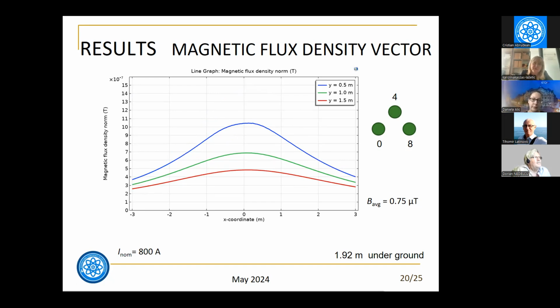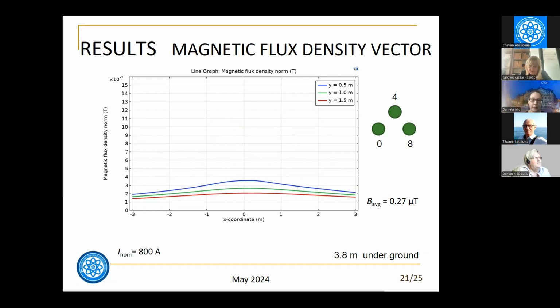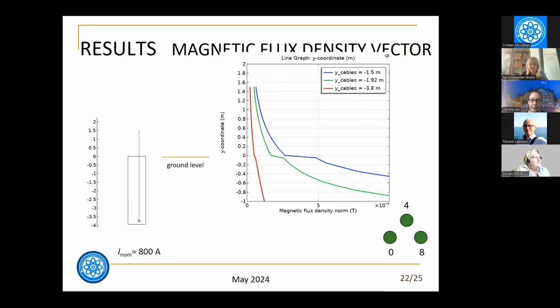When the cable is 1.92 meter underground, the values of magnetic flux density are less, and the average value is now 0.75 microtesla. And we have one more graph when the cable is at the depth of 3.8 meter under the ground, and we can see that above the Earth, the average value of magnetic flux density vector is only 0.27 microtesla.